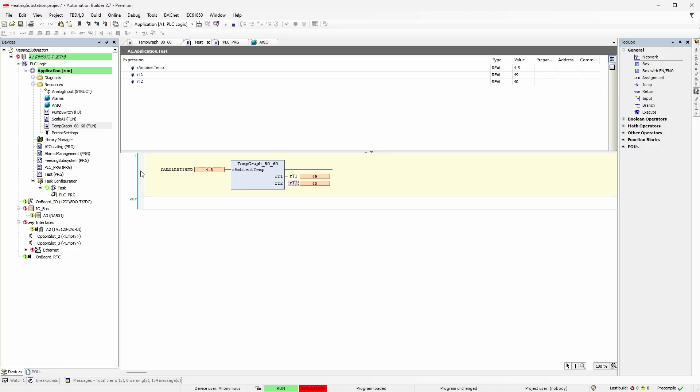Let's do some debugging. As a PLC programmer, you will probably spend more time troubleshooting than writing actual code. Automation Builder has a neat step-by-step debugging feature. To activate it, select a place in the program where you suspect the problem might be - in this case, we know the problem is somewhere in the temp graph function call. From the Debug menu, toggle a breakpoint. You will see that the PLC stops - but it's not stop mode as before, it's hold-on-breakpoint. Important note: you generally don't want to run breakpoint debugging on a PLC which controls a real process or machine. Pausing program execution can lead to unintended behavior, breakdown, or even fatalities. Be very careful. If you can, just use simulation.